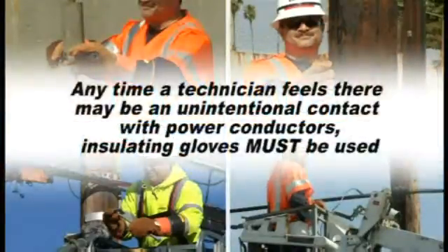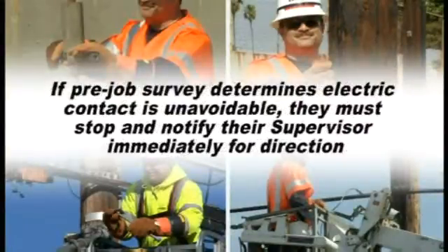However, any time a technician feels that there may be an unintentional contact with power conductors, insulating gloves must be used. If the technician's pre-job survey determines that electrical contact is unavoidable, they must stop and notify their supervisor immediately for direction.